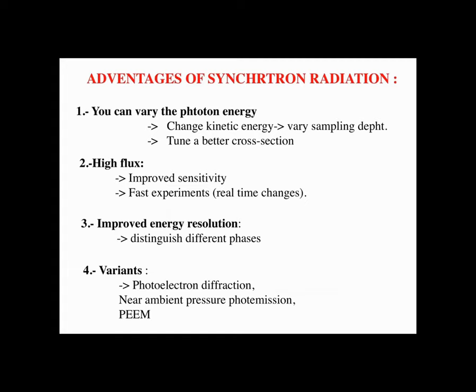You cannot buy a synchrotron, but you can improve the X-ray source of a standard XPS system. Some of the synchrotron variants can be done with standard XPS — photoelectron diffraction for example can definitely be done with a standard XPS system. The variations are small, which is why higher flux makes it much nicer, but the technique was discovered with standard XPS. You just need to be able to move your sample in all directions to find the maximum intensity — requiring a very precise sample manipulator to change angles.